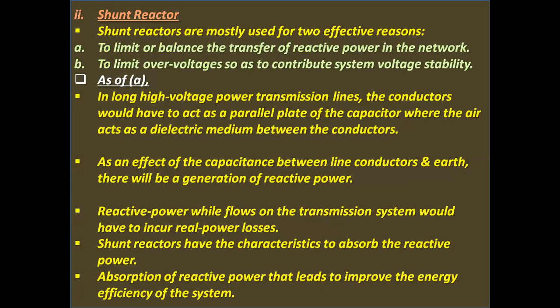Shunt reactor. Shunt reactors are mostly used for two effective reasons. One, to limit or balance the transfer of reactive power in the network. Number two, to limit over voltages so as to contribute to system voltage stability. As of (a), in long high voltage power transmission lines, the conductors act as parallel plates of a capacitor, where the air acts as a dielectric medium between the conductors.